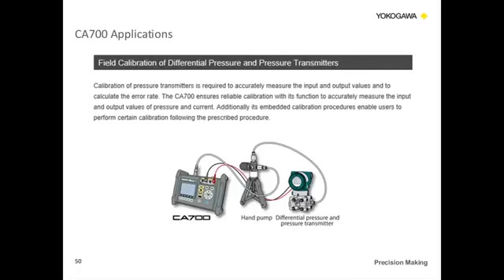Thanks, Tay. You're right. The CA700 is such a versatile machine that we actually see a lot of different applications. One of the primary applications, of course, is field calibration of pressure transmitters and differential pressure transmitters. A lot of times in the field with the competitive products, there's just not quite the accuracy to do a true field calibration. With the CA700, at 0.01%, instead of just doing a field verification, we are accurate enough to actually perform a full field calibration. So that's very critical for this product.